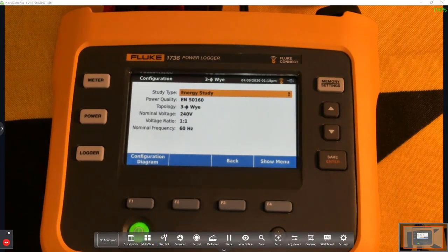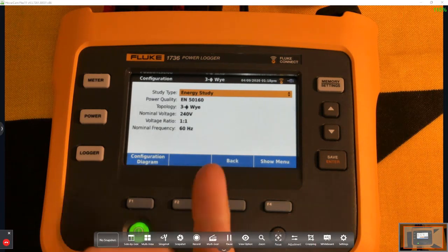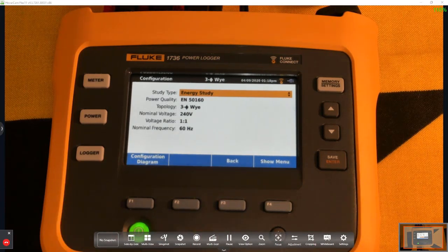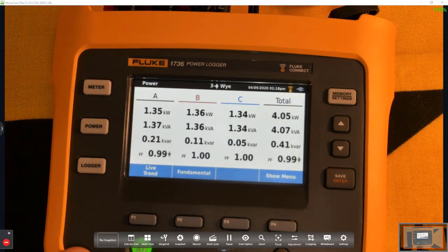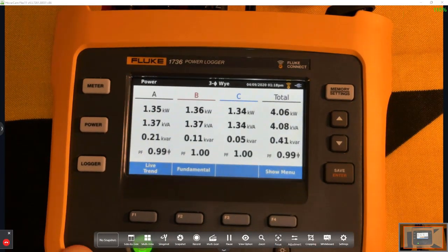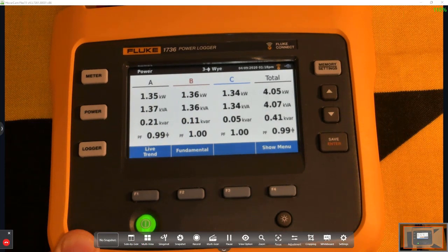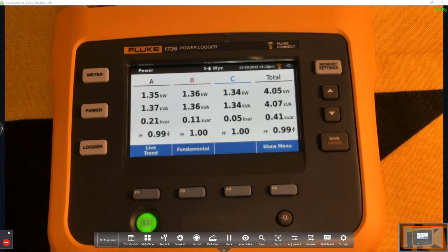Once you've gone through and selected energy study or load study, energy study still does all the same things, but it also includes power measurements, your kWs, your kVAR, and your power factor as well. So if you need power factor, you would definitely be doing an energy study. That's one of the key differences: you can do load study or energy study, but you won't get any power measurements if you're using the load study.